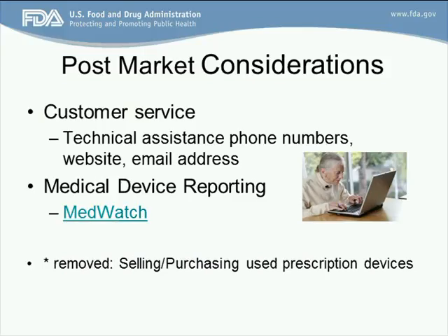There's the medical device reporting. Encourage people to report problems to MedWatch, and you can allow that. You can also say, no, we did not necessarily put that in the guidance. If you want to add that in, you are allowed to do that. We did remove in the final guidance document a section about selling and purchasing used prescription devices. We believe that industry really does not have a lot of control over where their products go after a period of time, and so we did take that out of there.